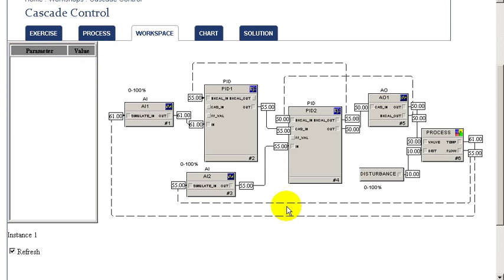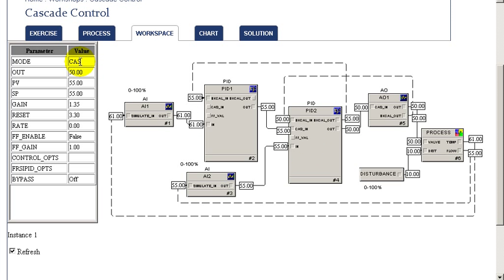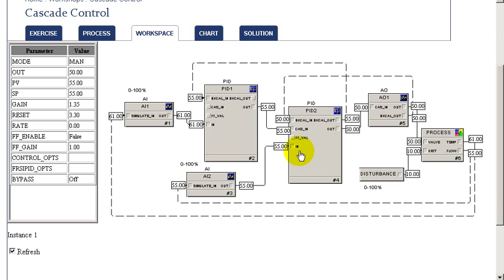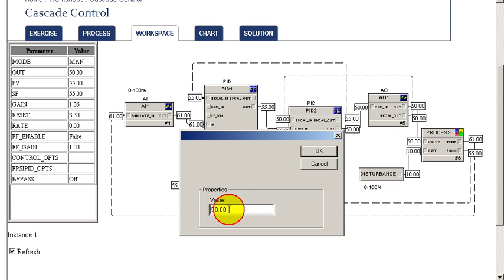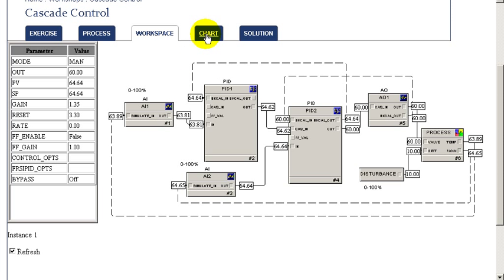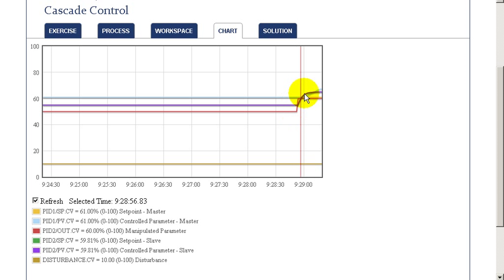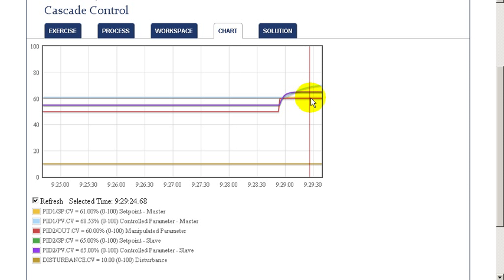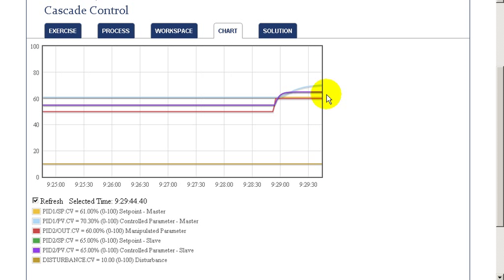Let's get started with our exercise. In the first part, we'll look at the process dynamics by putting our slave loop into manual and making a step change in its output. As we change the output of our slave loop by step, we can examine the process response. When the input changes, both process outputs do change, but the one used by the slave loop is much faster in responding. Looking at the chart, we see the faster responding parameter settle out quickly, while the other output is much slower to reflect the input change — that will be the input used in our master loop.